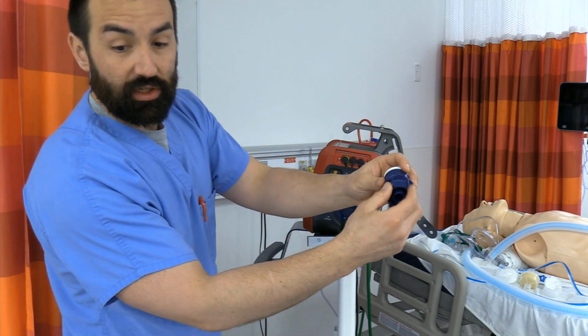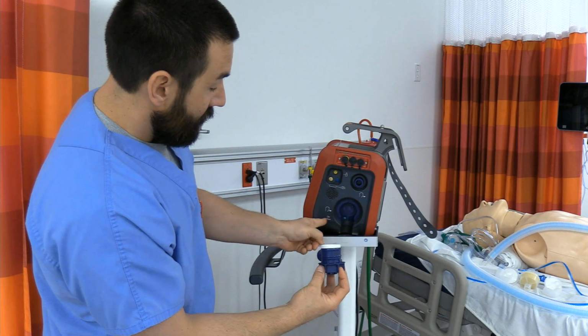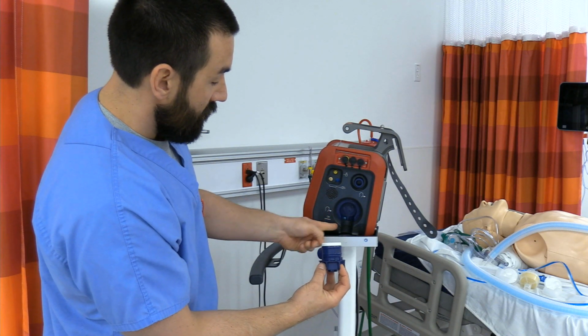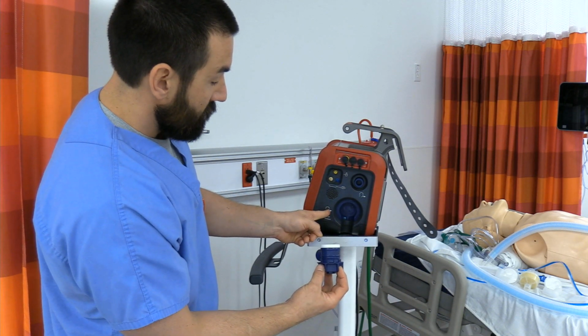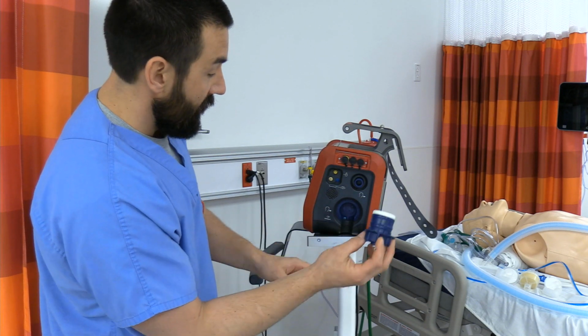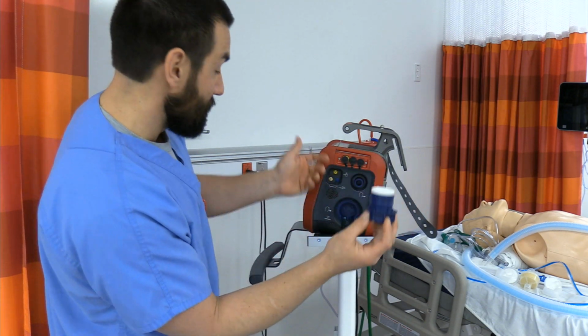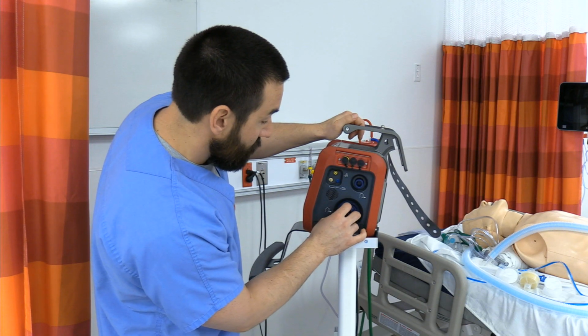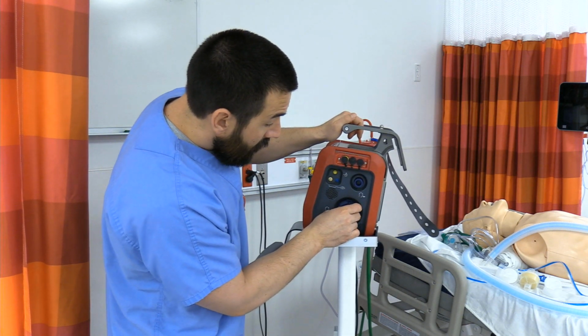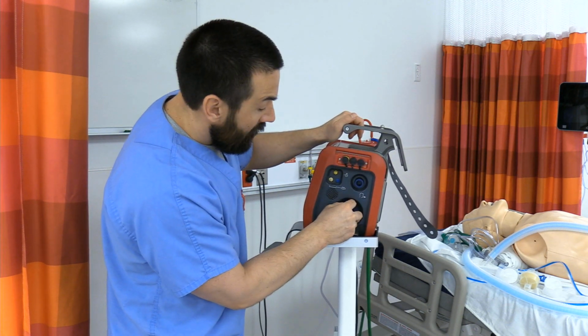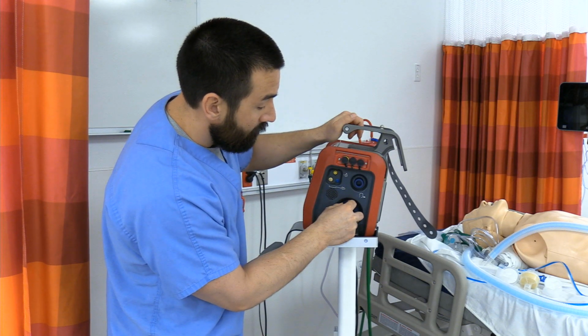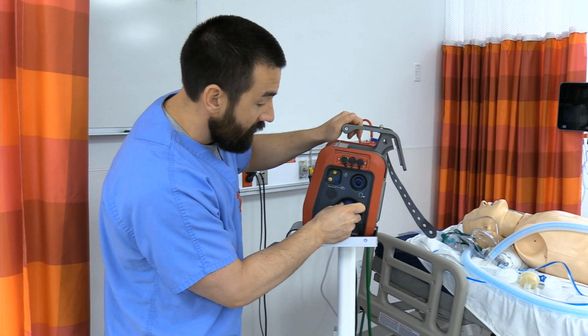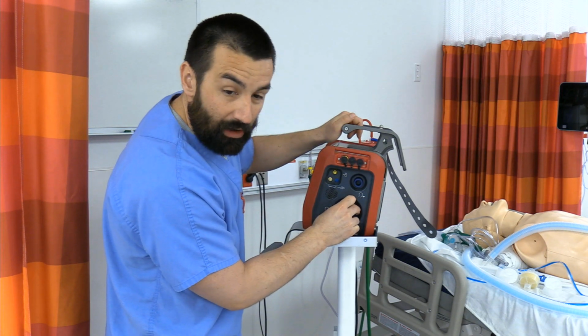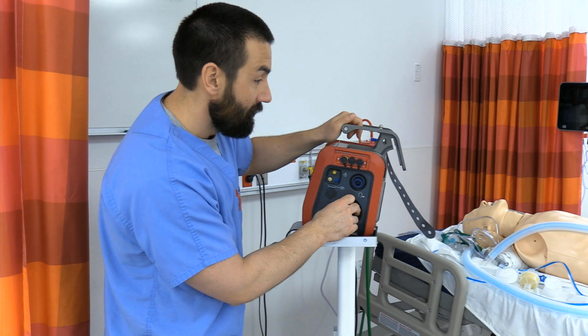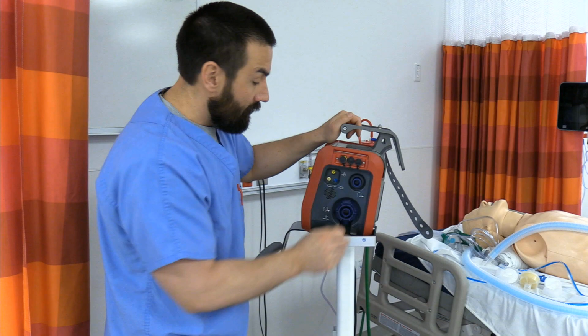So this piece is just going to twist and lock. We're going to go right here. You can see it says exhaust down here. There's a picture of a head with an arrow coming out, so clearly the expiratory side, and it's the only place where this is going to fit. So I'm just going to slide this in place. And this is going to just turn clockwise to lock in place. If you have a little bit of trouble and it's not going, sometimes you just have to turn it counterclockwise until you feel it set into those grooves, and then click and lock.